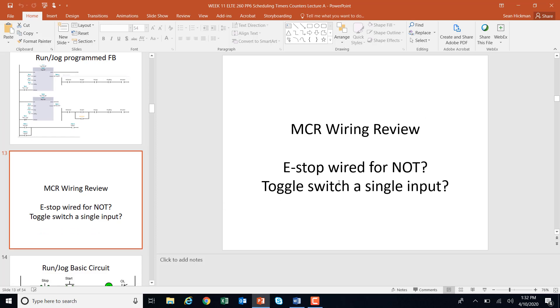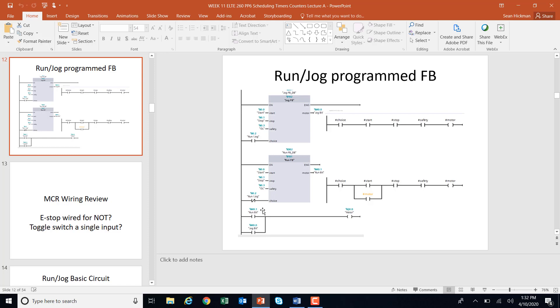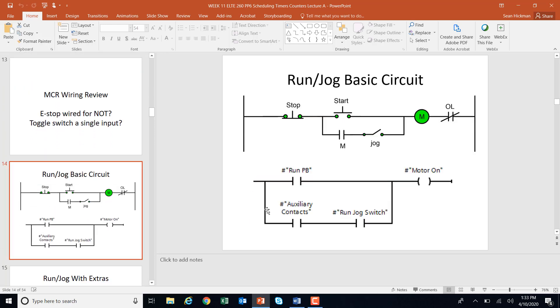Remember, e-stop is a normally closed contact, and we were using a toggle switch for a single input — that way only one of these conditions can be true at the same time. A better way to do the run/jog circuit is like we did in 131: a jog selector switch essentially enables or disables memory. If the jog switch is off, when you hit start you don't get memory. When it's on and you hit start, you get memory. This is the programmed version of that run/jog circuit.